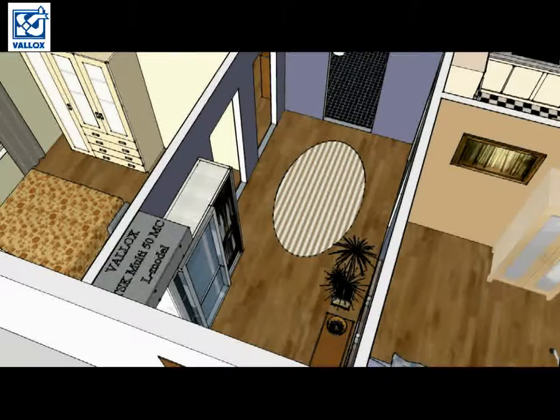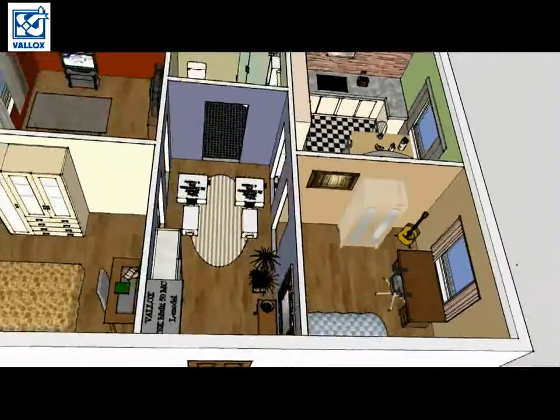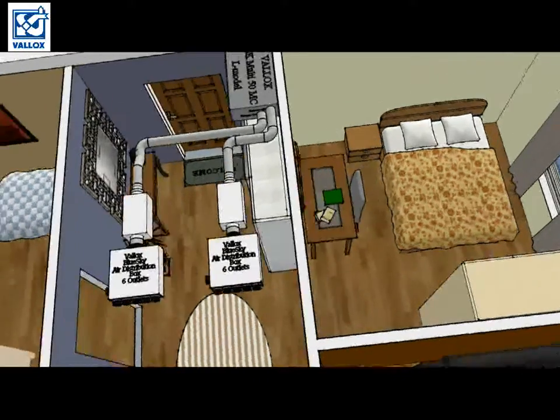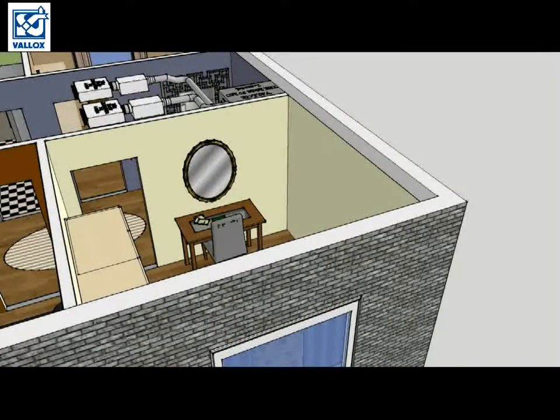Next we will install silencers. After that, we can install BlueSky air distribution boxes. Besides supply and extract air ducts, the ventilation unit also needs outdoor air ducts and exhaust air ducts. We already have supply and extract air ducts, but how do we get outdoor and exhaust air ducts to the outside? Fortunately, we don't have to take them to the roof. We are going to blow exhaust air outside from the apartment using the Vallox outdoor wall hood, and we will also get outside air to the ventilation unit from the same spot.